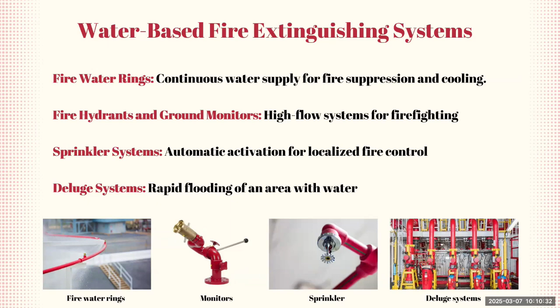Then we have sprinkler systems, which are not only in process plants but everywhere - for example in your offices, you would see these sprinkler systems in place, which spray water to control localized fire. Finally, we have deluge systems, which are a bit more complicated, involving rapid flooding of an area with water. A deluge system is very useful for process plants, where if we have a fire, it will flood the whole area with water.